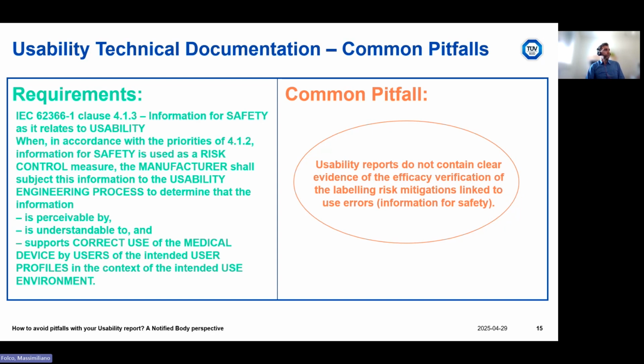Clause 4.1.3 is related to the information for safety, so labeling elements used as a risk control measure. When labeling elements are used as a risk control measure, the manufacturer shall submit this information to the usability engineering process to determine that the information is perceivable, understandable, and supports correct use by the intended users in the intended use environment. What does it mean? It means that when information for safety, so the labeling elements, is used as a risk control measure, it has to be validated for its risk mitigation effect, as I already said before. And the usability engineering process shall confirm that this information is perceivable, understandable, and supports correct use.